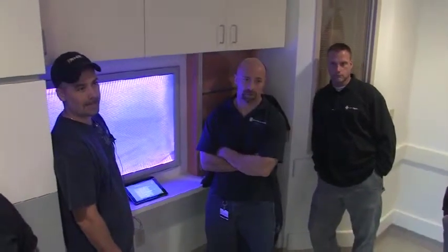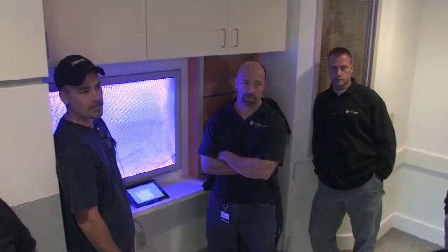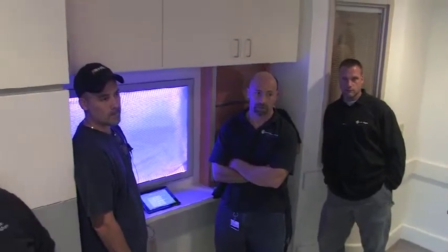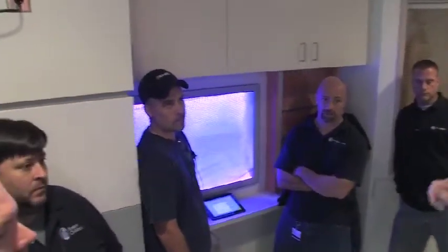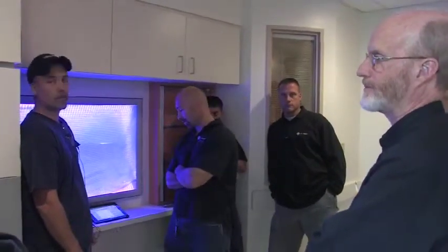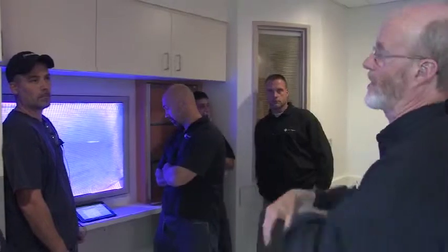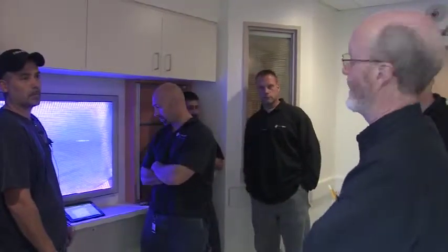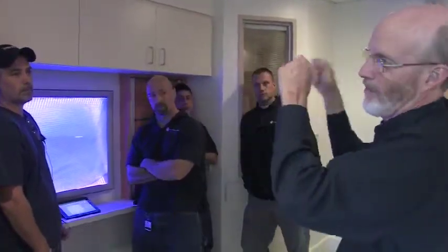The last time I did something with the balancer up on 11, they had put a fan power box in, that's what we were adjusting. I had to get up there when too much air was blowing, so I had to open up and there's a little circuit board. I took a little tiny pocket screwdriver, and you can adjust the fan speed on the circuit board. It's not something that's obvious. If somebody didn't know what they were doing, they wouldn't have any idea, because you gotta open up these little panels.